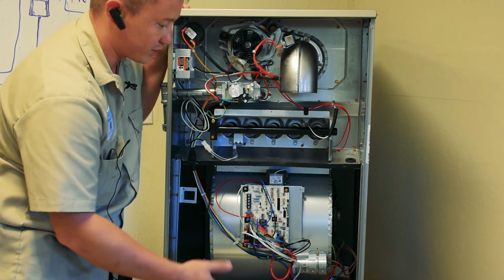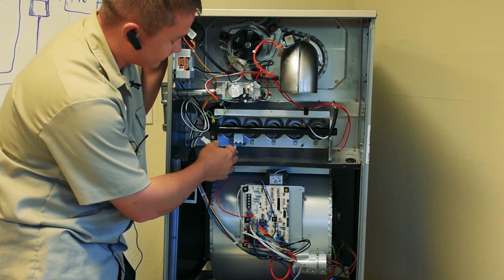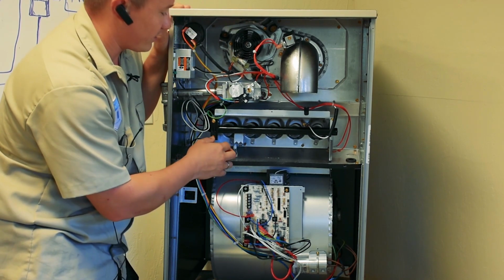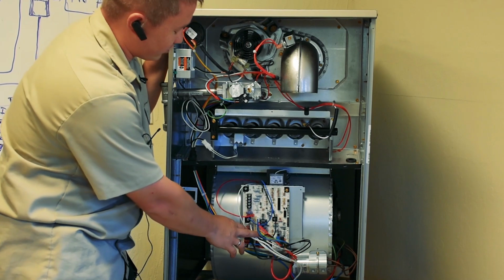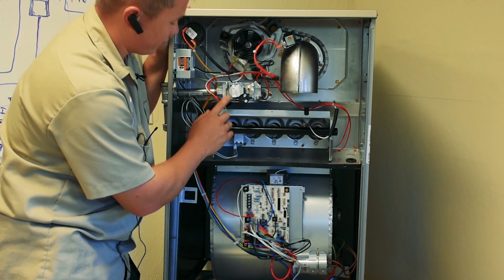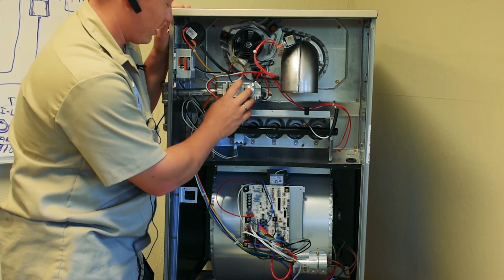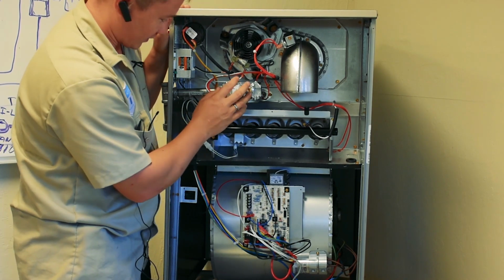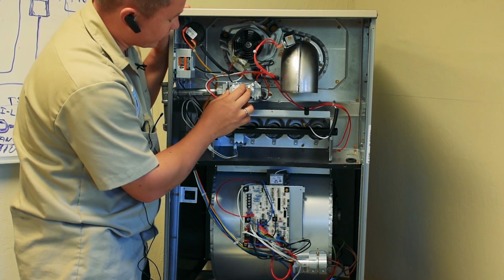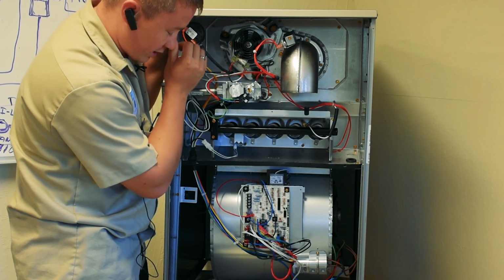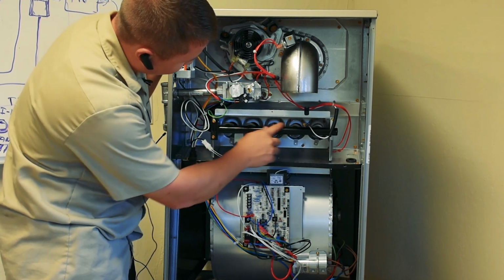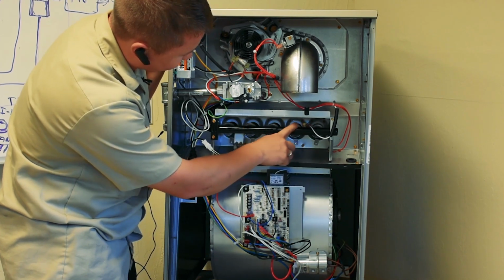It's running for like 30 seconds, igniting the igniter. Then after 10 or 30 seconds, the control board will send the power, 24 volts AC, to the gas valve. This gas valve has just one solenoid, which will open the main valve, and the whole pressure of gas will go through this black pipe to the gas injectors.